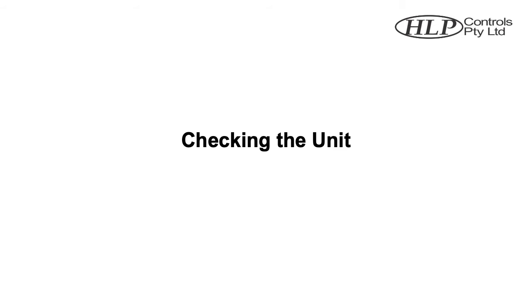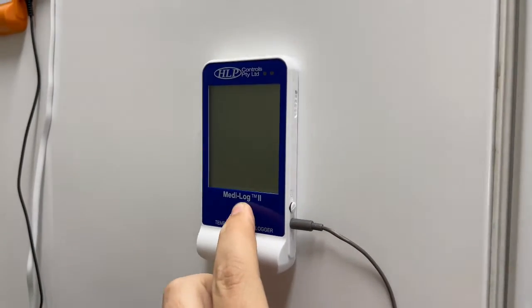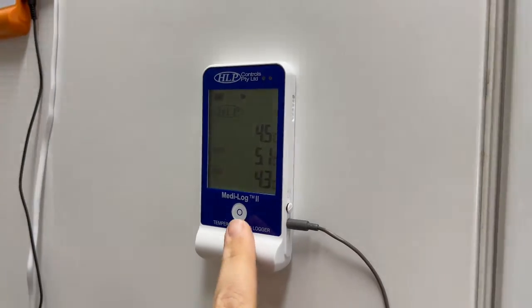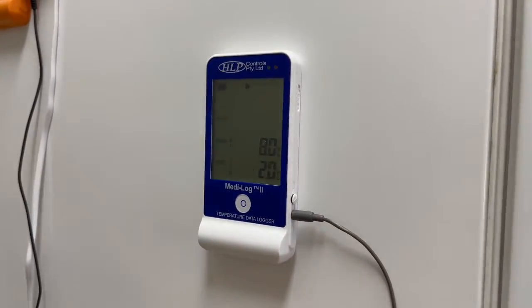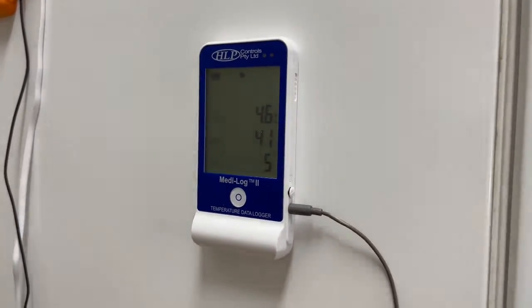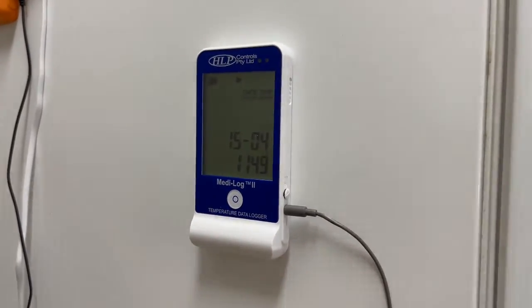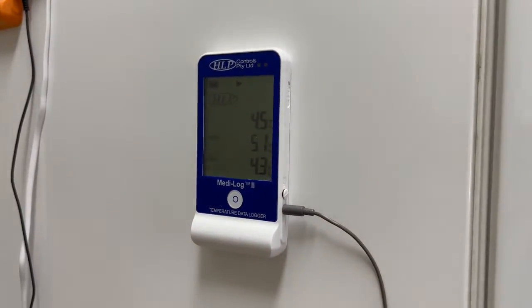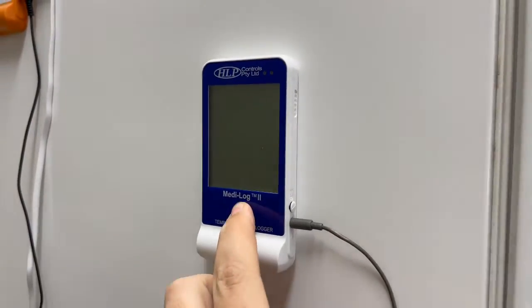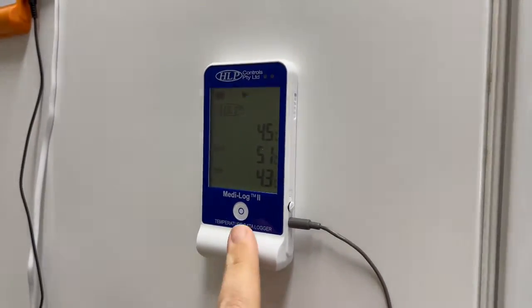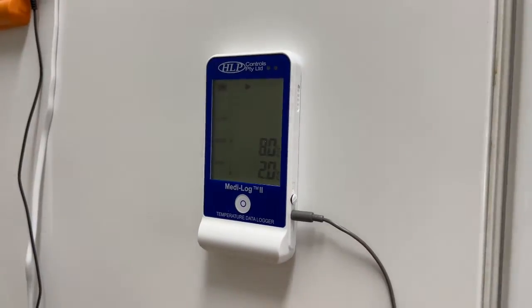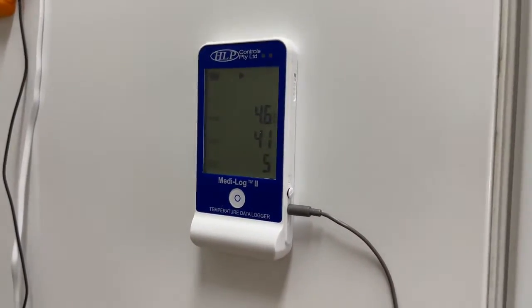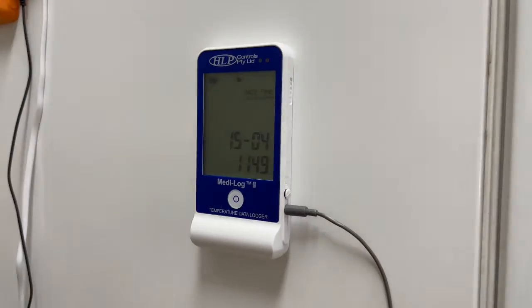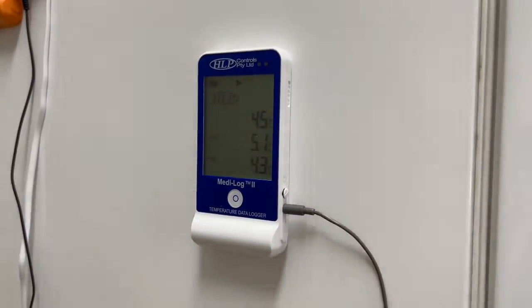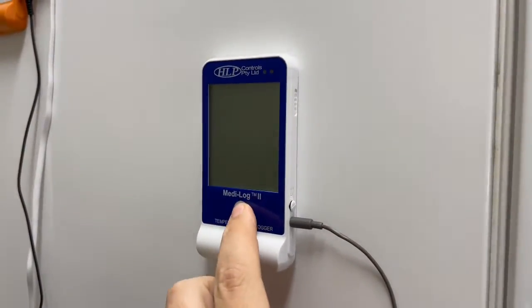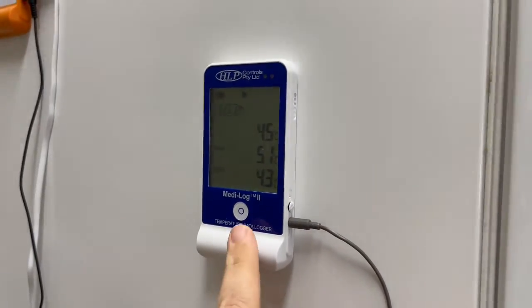Checking the unit. You are able to check the unit at any time by single pressing the center button. The unit will display a play and battery icon on the top of the LCD screen to represent the status of the unit. Pressing the center button will change between the following 4 screens: the current and minimum and maximum temperatures from the current logging period, the current min-max alarm settings, the average temperature, count of current logs stored, and the minute interval settings it is currently recording with. The final screen will show you the date, month, and time the unit is currently logging with.